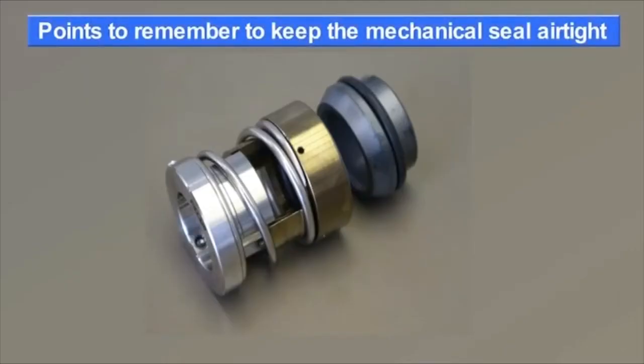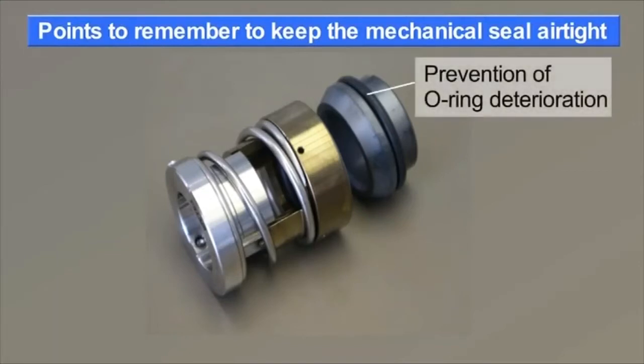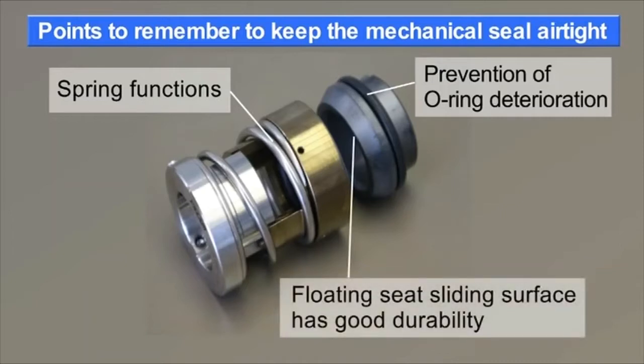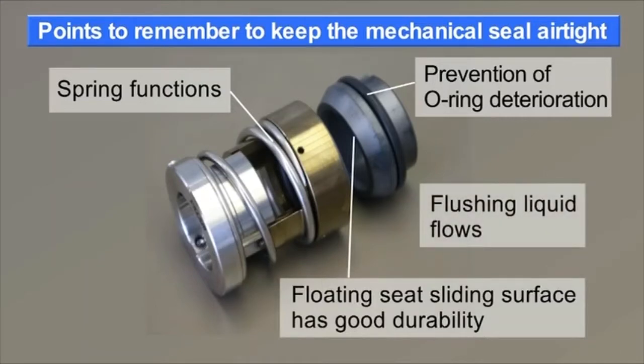Key points for maintaining mechanical seal functions are that the O-ring does not deteriorate, the spring which presses the sliding surface functions well, the floating seat's sliding surface has good durability, and flushing liquid used for cooling and cleaning the seal part keeps flowing.